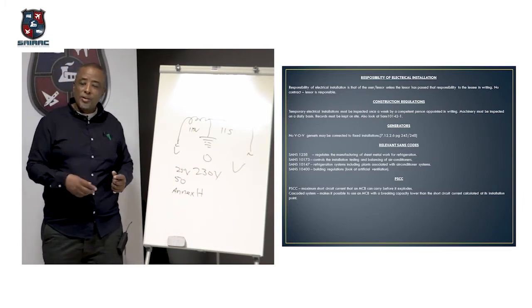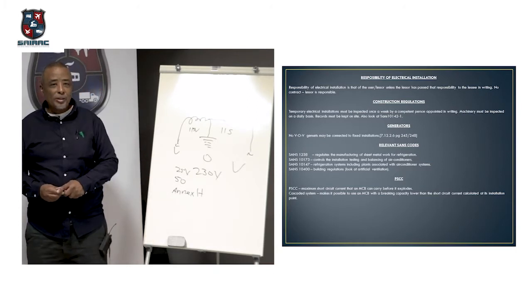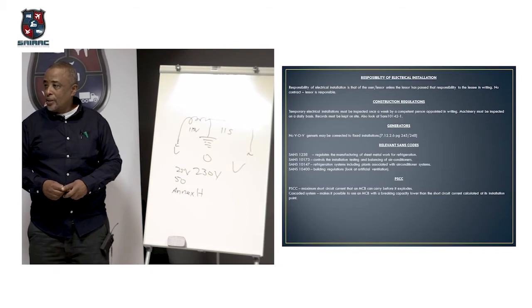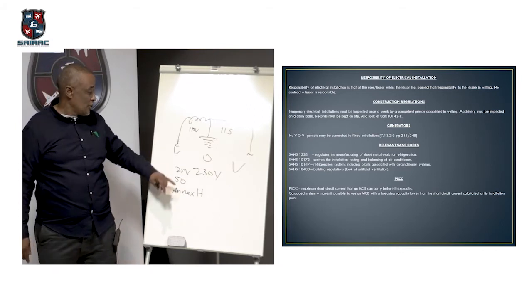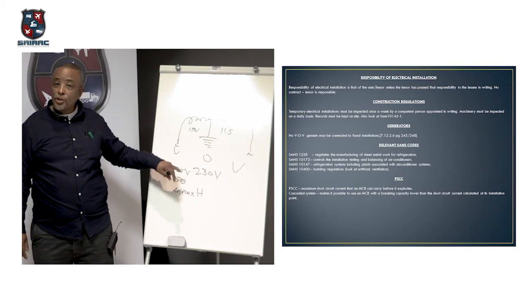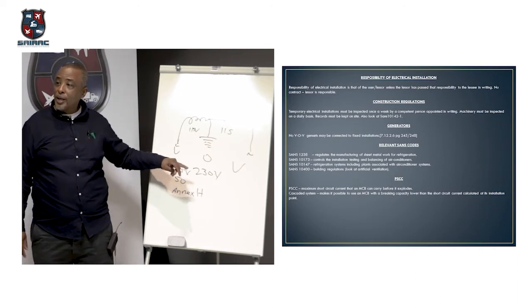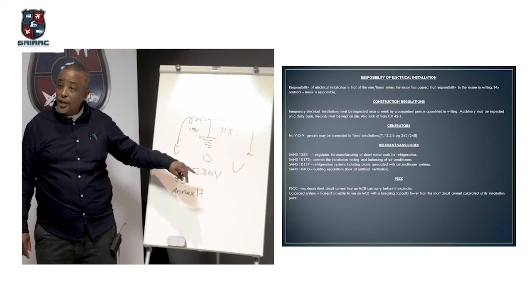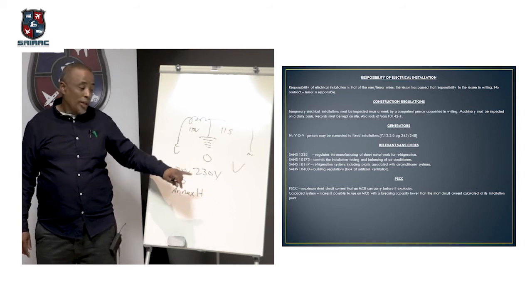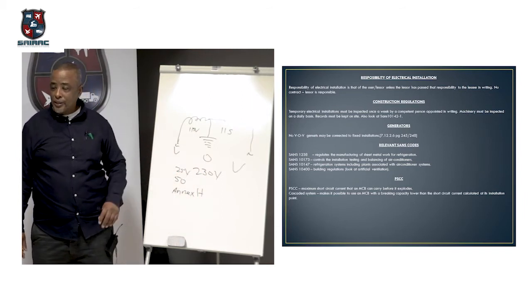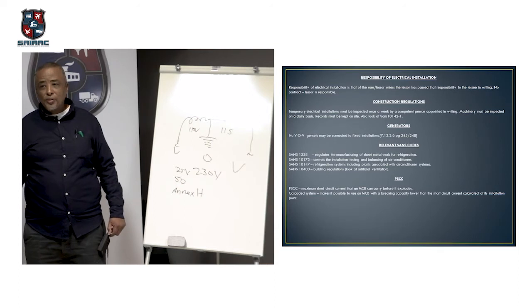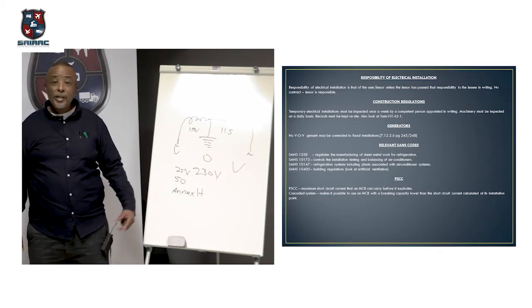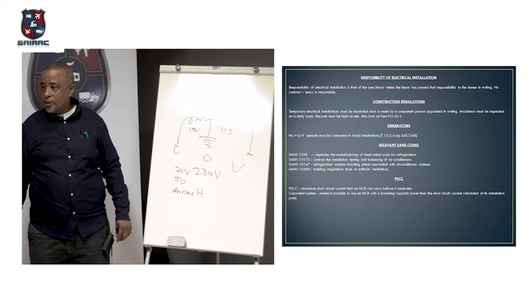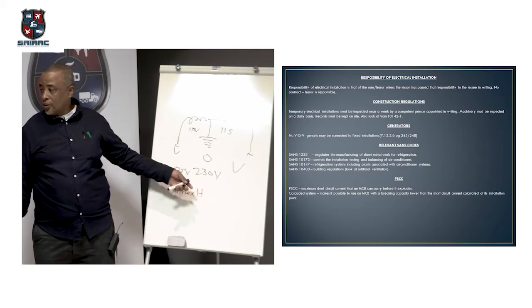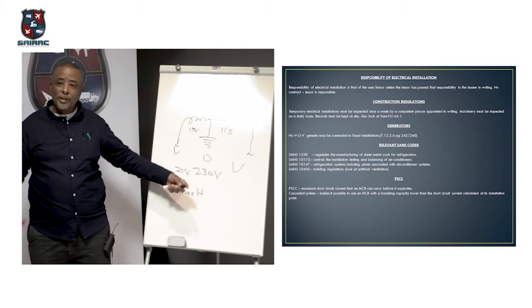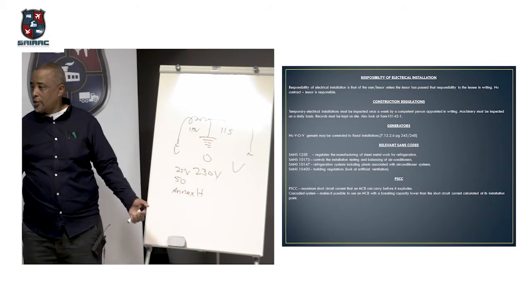And most of the time when we do go out, guys are stealing cables and they steal the earth wire from the transformer. That's why I said sometimes it's beyond your control. So you notify the municipality if your elevated neutral to earth voltage is about 25 volts and more. If it's 50 volts or more, you switch off the installation. Okay. Don't consider the person's koi and the meat that they have, switch off. Like I said, once again, sometimes it's beyond your control. Most of the time it's on the municipality side, on the supply side. They've stolen the earth from the transformer, so there's no protection. Okay.